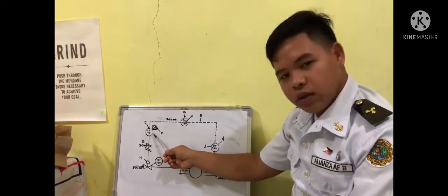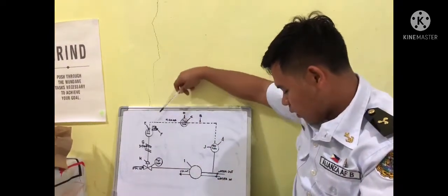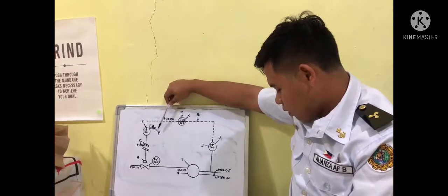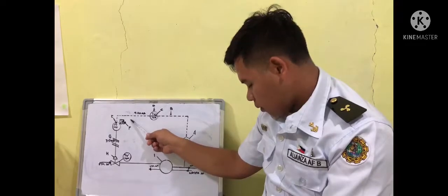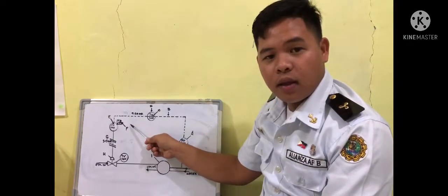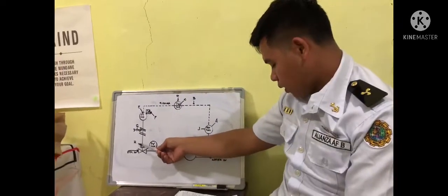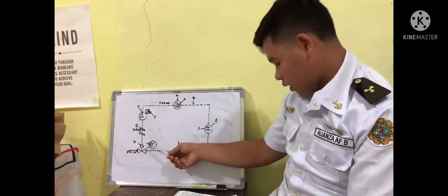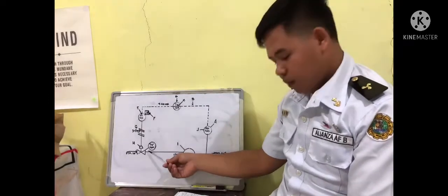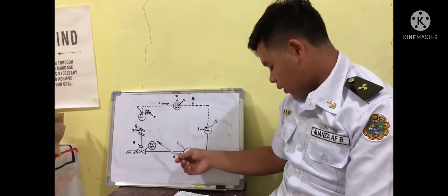The functional identifier, the transducer, converts the electronic signal to a pressure signal, and is indicated by a square containing the letters I and P, with a line with diagonal marks. The letter H represents the actuator. The half semicircle and the line pointing downward indicate the globe valve.